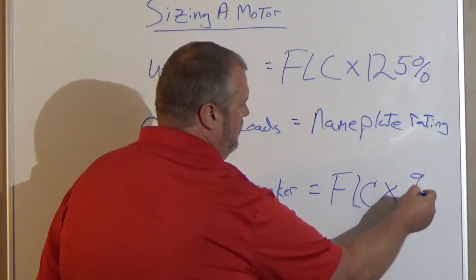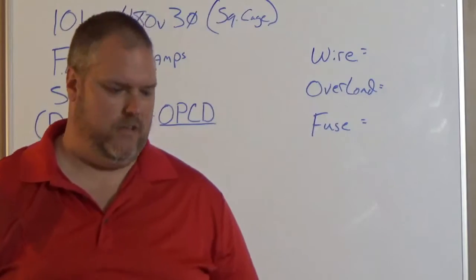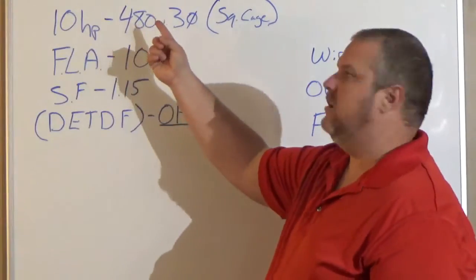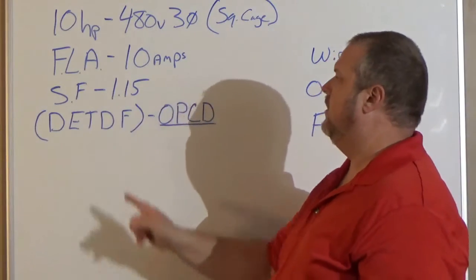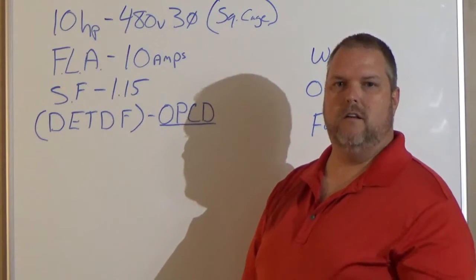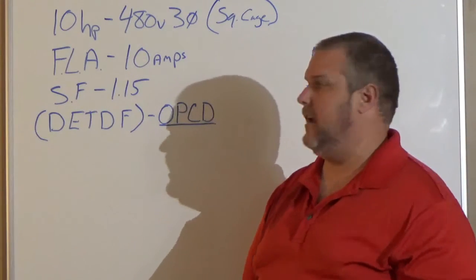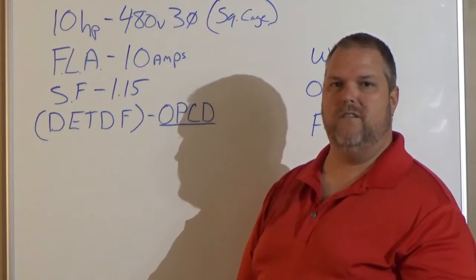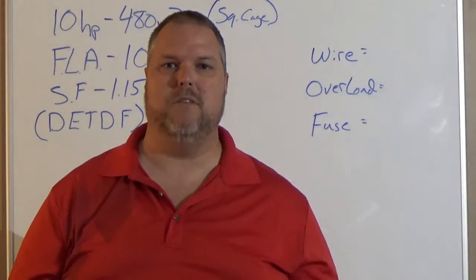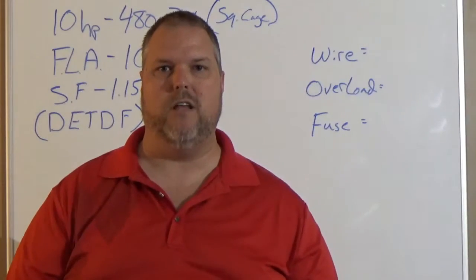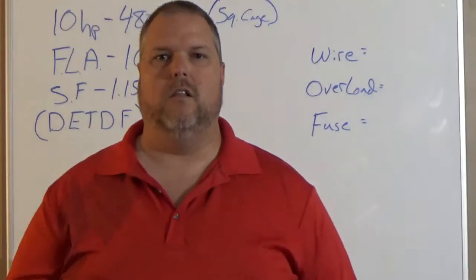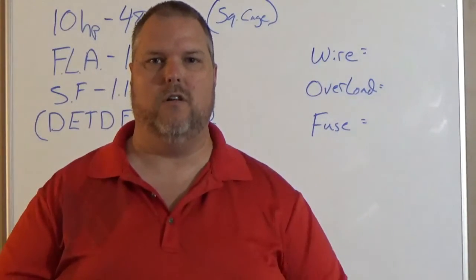We have a 10 horsepower, 480 volt, three-phase squirrel cage motor. We have a nameplate rating or a full load amp of 10 amps. So this 10 horsepower motor is drawing 10 amps. We have a service factor of 1.15. And this is going to be a dual element time delay fuse. So this is all the information we need to know to size our wire, our overload, and our fuse. Let's break it down. We'll do wire first, then we'll do overload, then we'll do fuse.